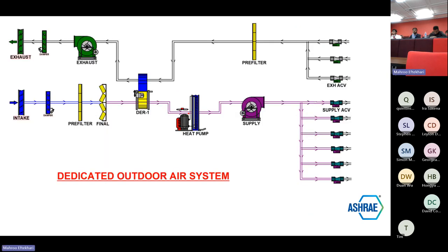The other side of it was a dedicated outdoor air system. We designed it for 30% more than 62.1, and made sure that happened by having dedicated outside air. We decoupled cooling from the ventilation system so we could always maintain that ventilation rate. The only place we vary the ventilation rate is in the learning center, where occupant loads vary quite a bit. This was the strategy to get us to proper ventilation.